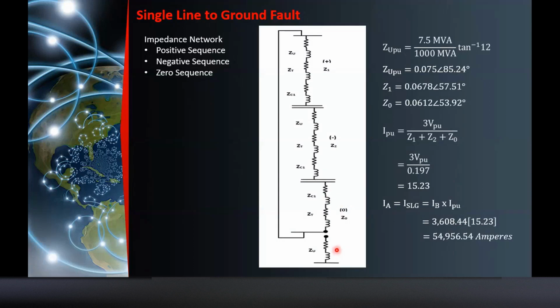Sa cable 1, Z2, sir, bakit po putol? Mapapansin nyo dun sa diagram, naka-delta Y, grounded. So, yung zero sequence, hindi pupunta ng utility. So, pag in-add up mo yan, Z1, Z2, and ZO, yan. So, since parehas lang yung Z1 and Z2, you will get, yung binanggit ko kanina ng formula, your IPU, pagdating sa single line to ground fault, is 3 EPU or 3 EA, yung kaninang sample ko, divide by Z1 plus Z2 plus ZO. You will get 3 EPU divide 0.197 is equals to 15.23. Ang kagandahan ng per unit, mapapansin nyo, yung I-base na ginamit nyo, kahit single line to ground fault na, yun pa rin. So, may single line to ground fault at 400 volts bus is 54,956.54 amperes. Okay?